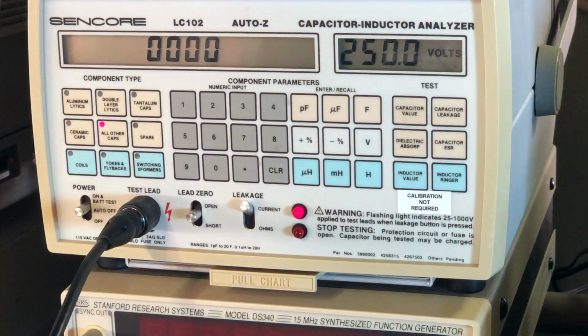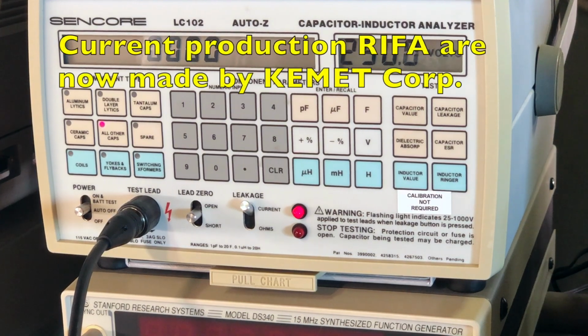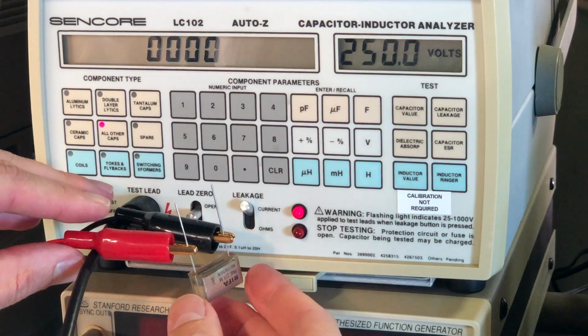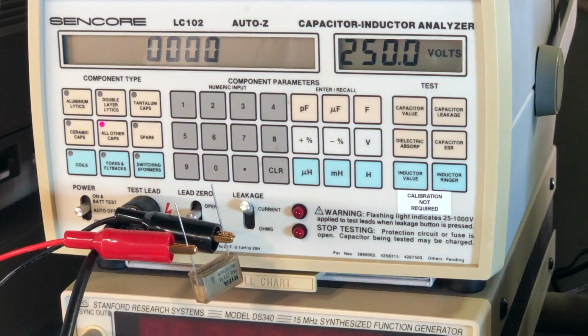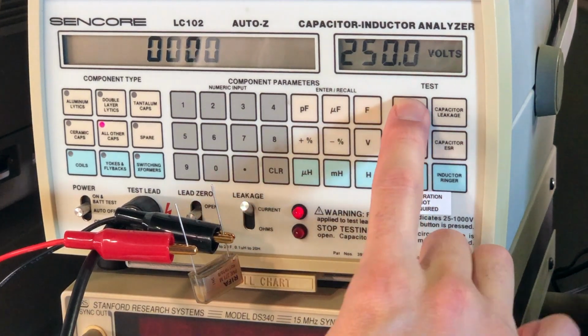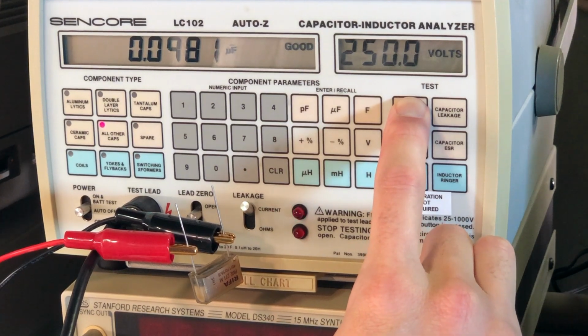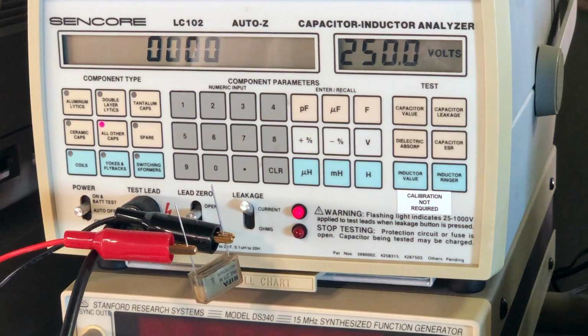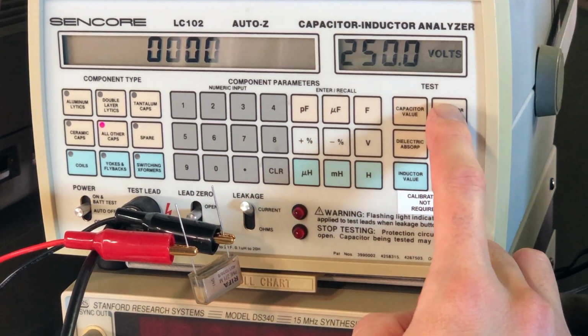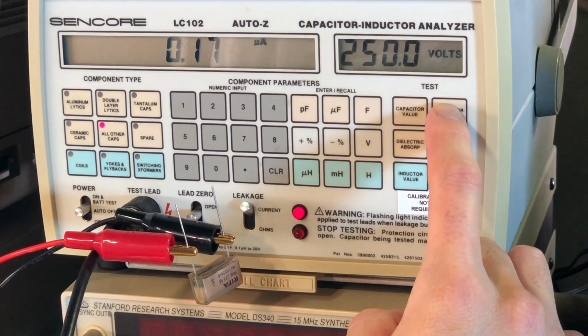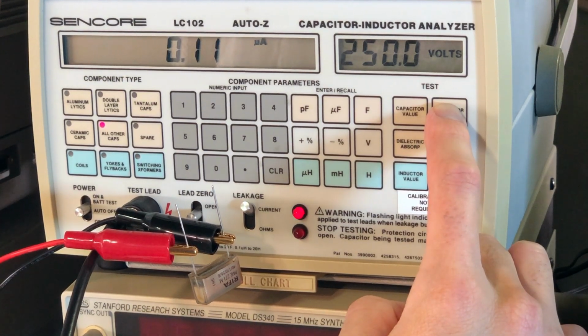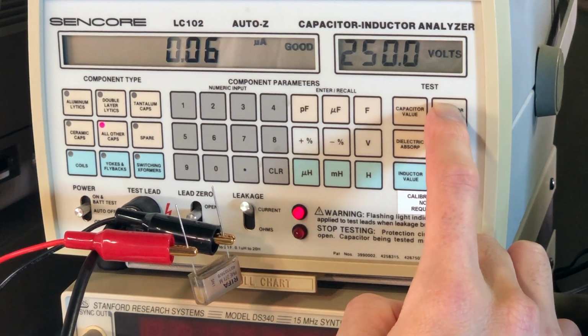Now let me grab one of the new capacitors, just like I installed. So we can see that right here. And these are modern production. Even though it says RIFA on it, I have not had any issue with these current production capacitors. They seem to work very, very well. If we do a capacitor value test, you can see 0.0981, so right at 0.1 basically, so no problems with the value. And if we do a leakage test, we have 0.17 microamps, 0.11, dropping down, 0.06, and now it does say good on the display, 0.09.